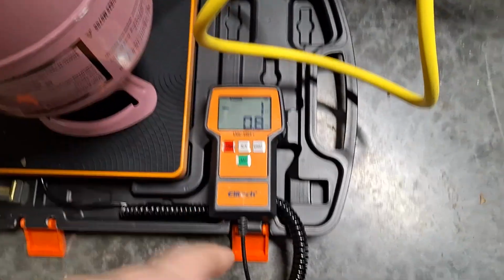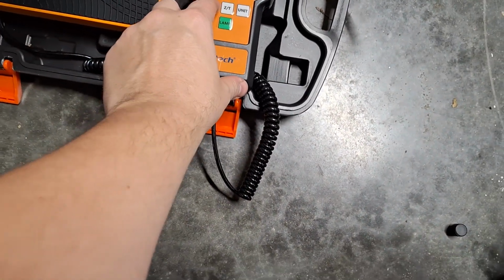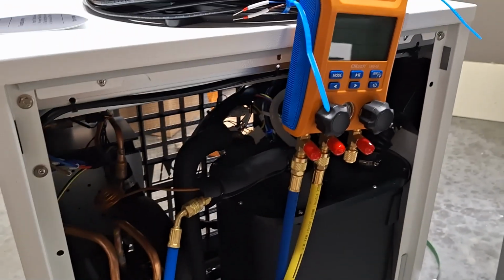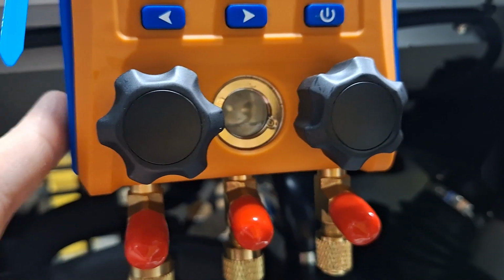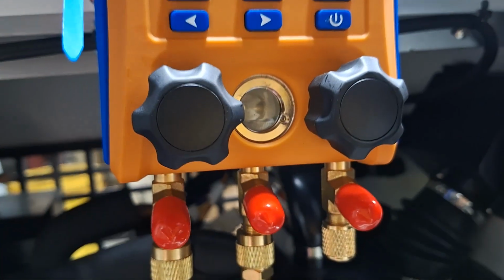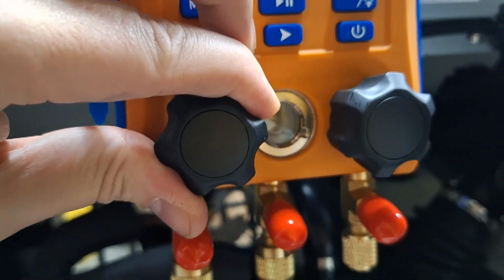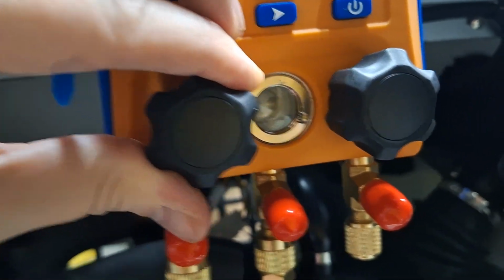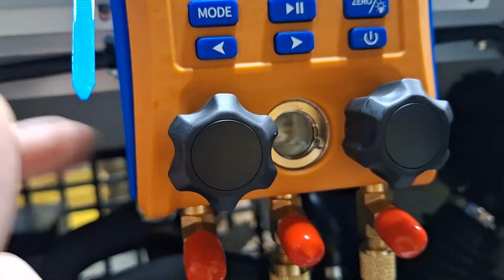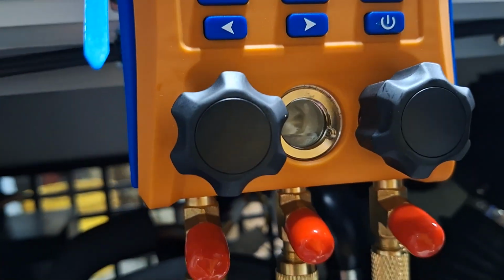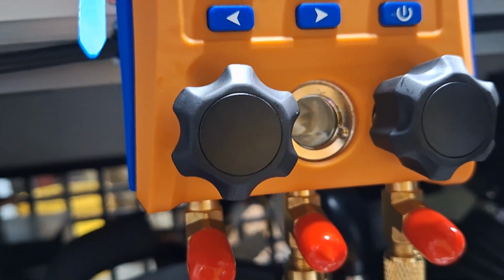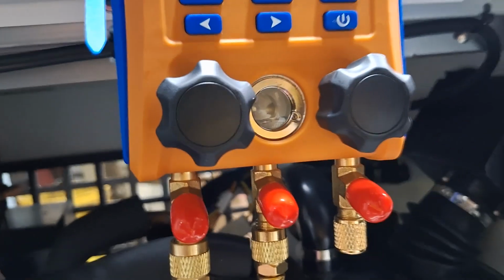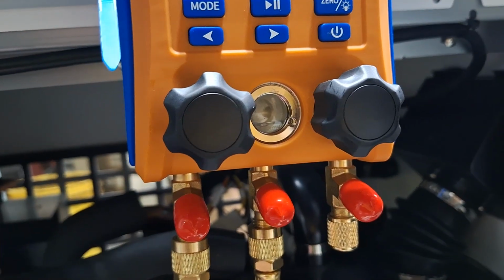You can probably see on the scale here that I got 1 pound, 0.8 ounces. It's a little bit over what I was going for, but that's because a lot of the liquid that came out of the tank actually ended up inside the gauge, where you can see it with the gauge sight, and that needed some time to convert to gas before it entered into the chiller. And using the weigh-in method like we're doing here, it's pretty accurate. It doesn't have to be 100% spot on.